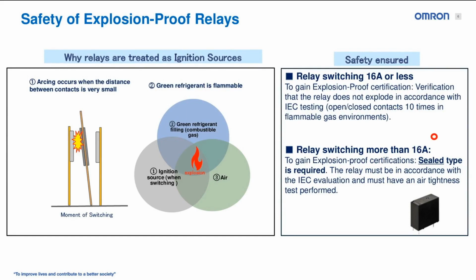But when we're looking at more than 16 amps here on the bottom, we do have to deal with a sealed type relay. So to gain that explosion-proof certification, a sealed type is required. That relay must be in accordance with that IEC evaluation and must have an air tightness test. So it is completely sealed, gases cannot get within it, and that arcing will always have isolation from the external environment. This is where a lot of the ground is untapped for relays, which are considered the ignition source. So we are looking to expand in both regions, but primarily for new products in the 16 amp, more than 16 amp sealed relay category.